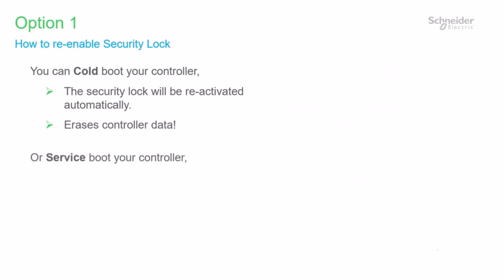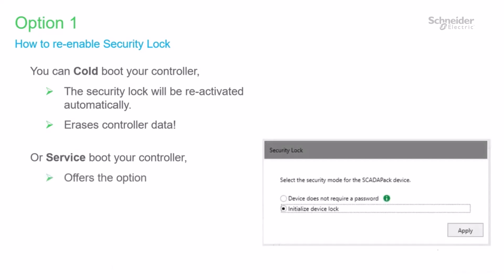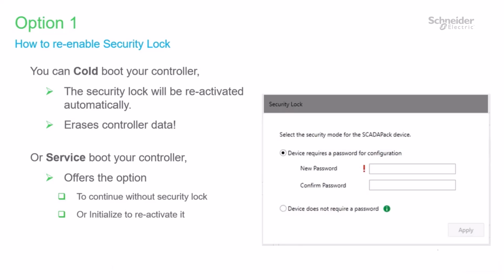So we also have the option of doing a service boot. When we go online with a service boot, we'll be presented with two options: one, to keep it with no password required, or the other, to select Initialize Device Lock. When you apply that, the dialog appears again, where we can apply a password or decide again to disable it. The advantage here is that the controller's data has been retained.